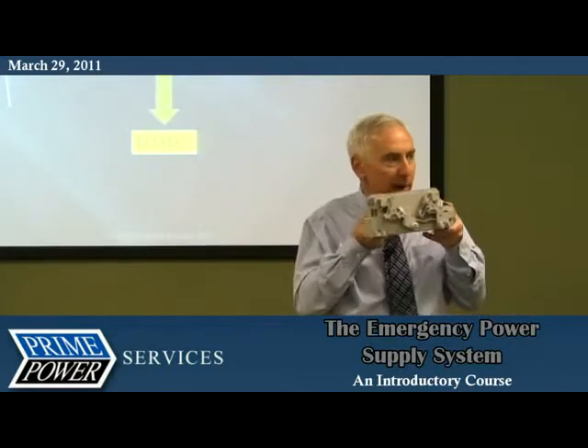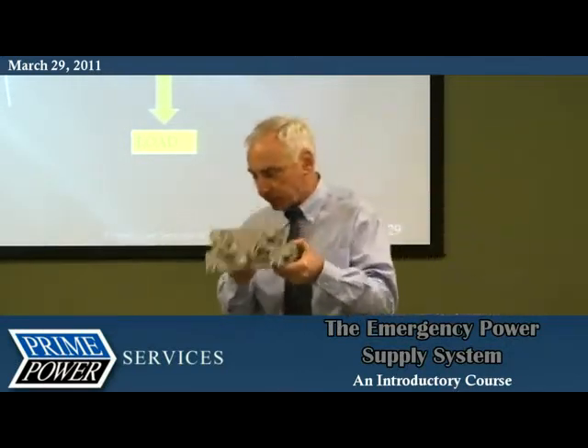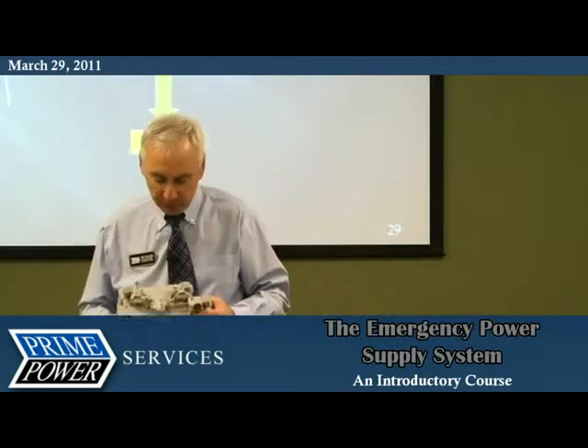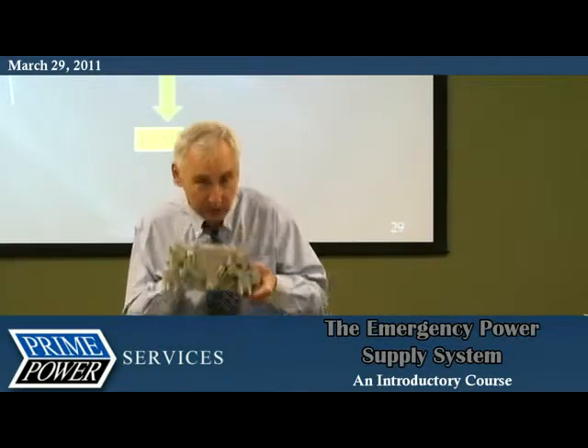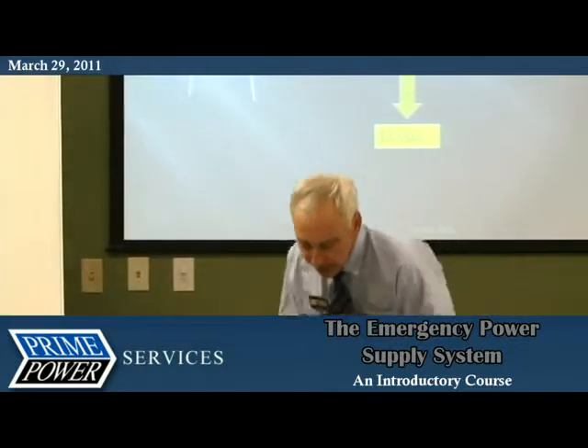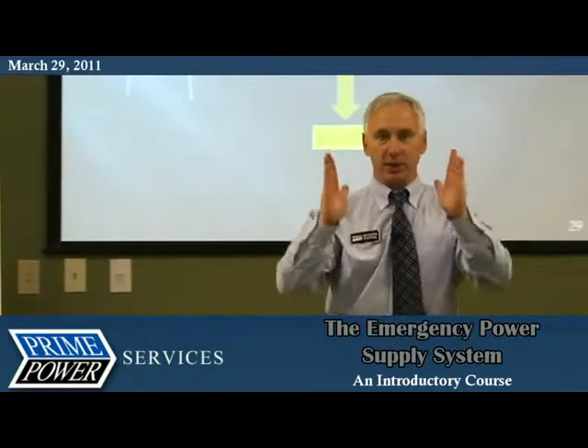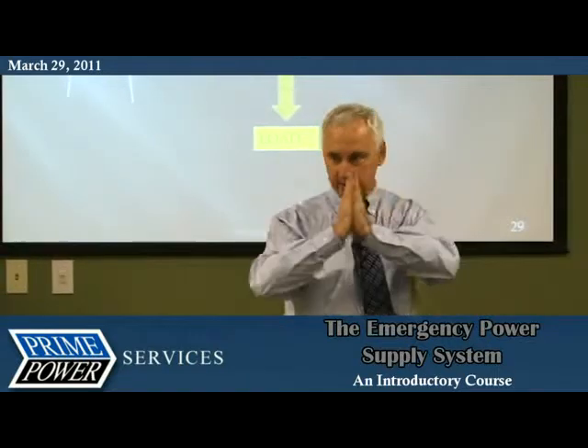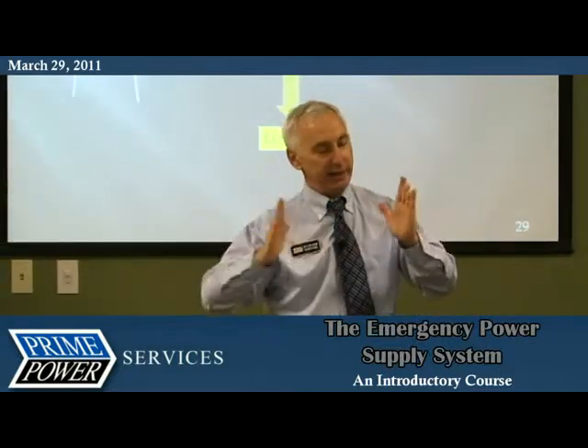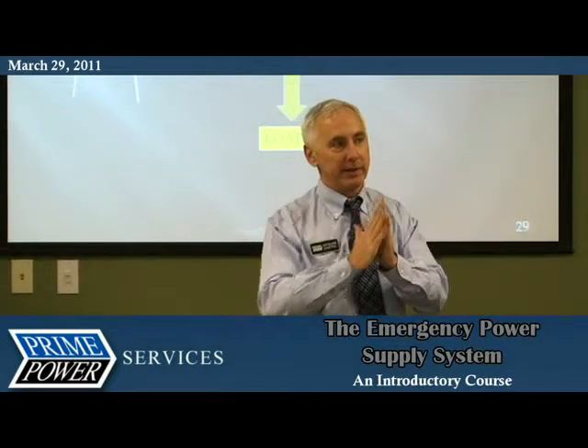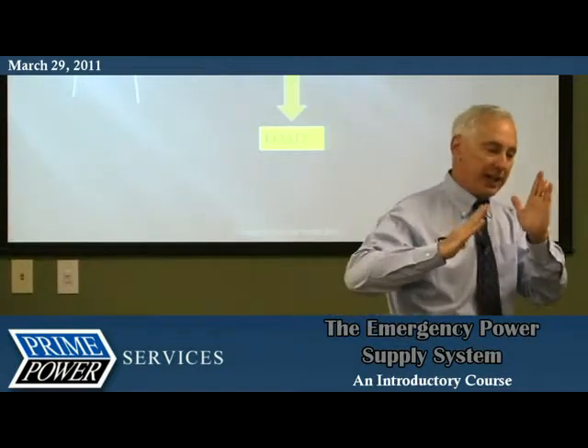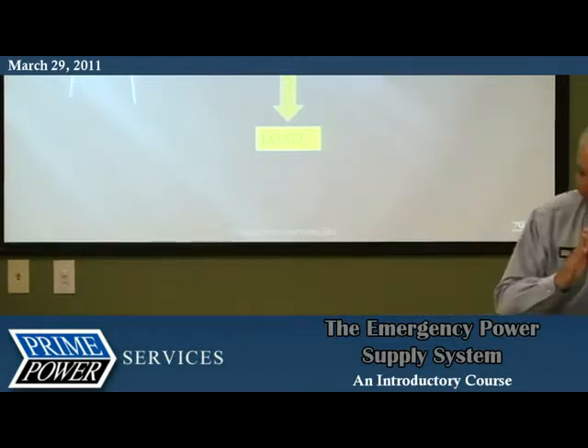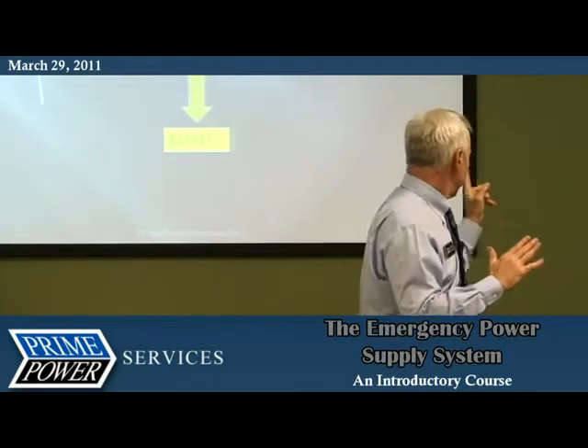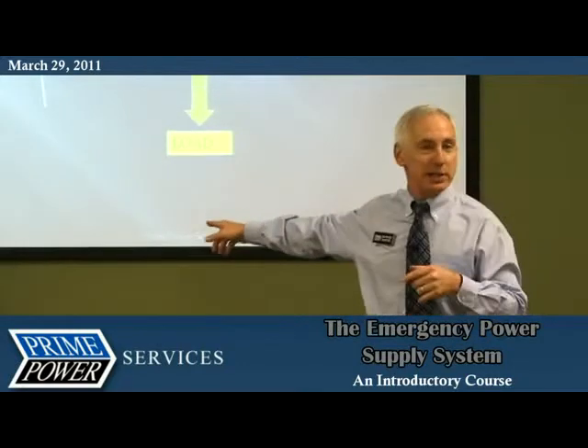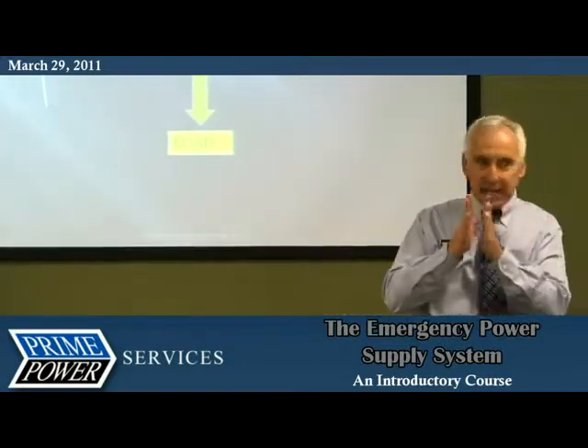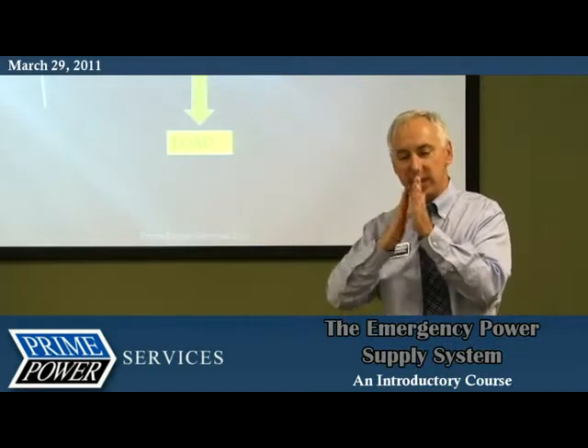One other simple reason why we operate this thing every month: when these contacts come slamming together inside, they don't just hit, they skid and wipe against each other. That's true of light switches, circuit breakers, any set of contacts. They don't just hit, they're designed to skid slightly.